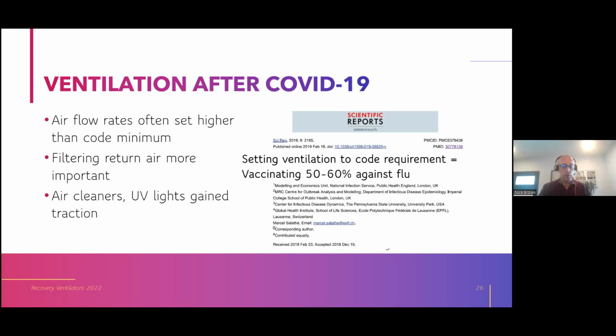And so some building owners chose to set their airflow rates higher than code minimum, more dilution in their spaces. Others upgraded their return filters from MERV 6 to MERV 13. Filtering that return air made a lot of sense, especially since MERV 13 filters pull airborne bacteria and viruses, particles in that PM 2.5 size range, out of the air effectively, whereas 6 and 8 don't. And then even air cleaners and UV lights started to really gain traction. They'd always been around, but I would argue that we can sell these types of systems that have enhanced indoor air quality benefits better than ever.